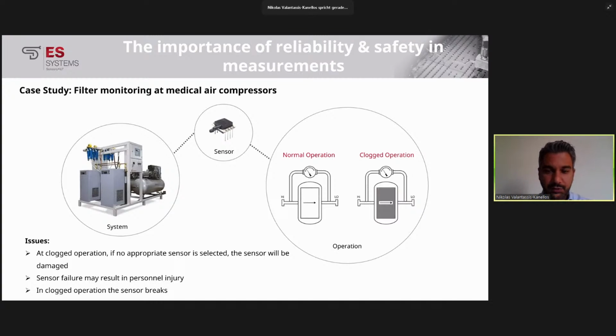Now, it is important for this application, for example, to pick the right sensor, because with a differential pressure sensor, in nominal operation for the filter, this differential pressure will be very small in measurement, while in clogged operation, this differential pressure can be very high. Usually what happens in this operation is that the differential pressure sensor at clogged operation is getting damaged and even breaks.